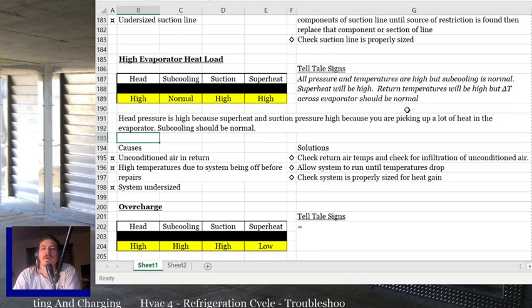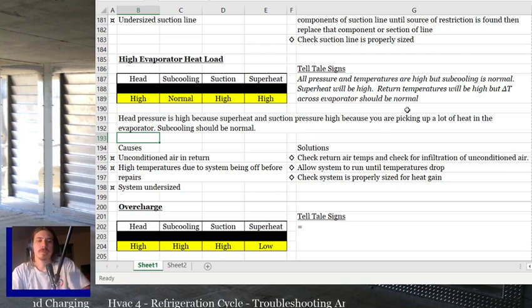So that's basically all there is to it. The causes of that are unconditioned air in the return, which is a really common issue, especially with ducts in an attic. If the return air duct is leaking and you're getting 100-degree attic air mixing in with your return, then you're going to have high evaporator heat load, and that system's not going to work real good. That's your most common high evaporator heat load outside of they haven't ran the system for 3 days for whatever reason. High temperatures due to the system being off for repairs or for whatever reason, or the system's undersized. The system's just way undersized. You'll have a high evaporator heat load on any hot day, basically.